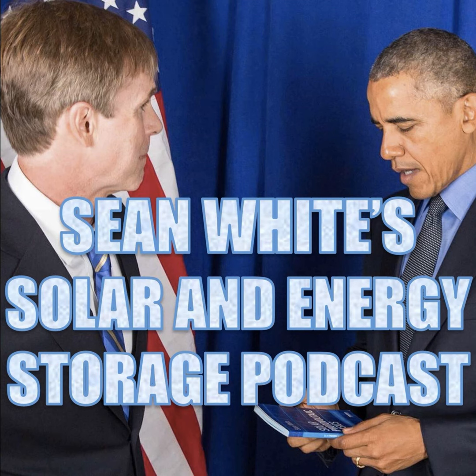And so what we did is we said, okay, we'll use the tap rule and we'll pretend like the PV system has the same fault current characteristics and capabilities as the utility. Now, does it? Of course not. We generalized Article 705 to all power sources, so you could have a power source like a synchronous generator or something like that, even though they're rare, that could be feeding current and fault current into that feeder. And then these tap rules would be preserved because they're still very conservative even for a generator. And so if it's a short tap, you're normally not going to have a problem. If it's a longer tap, it's just a little more than the rating of the circuit breaker.